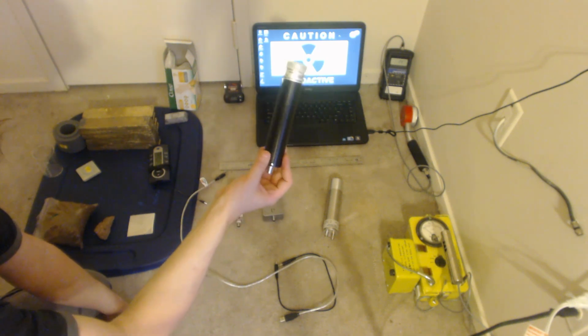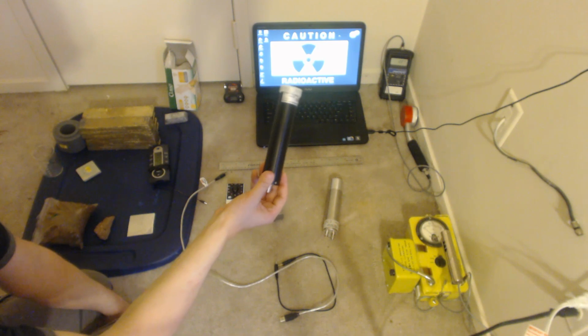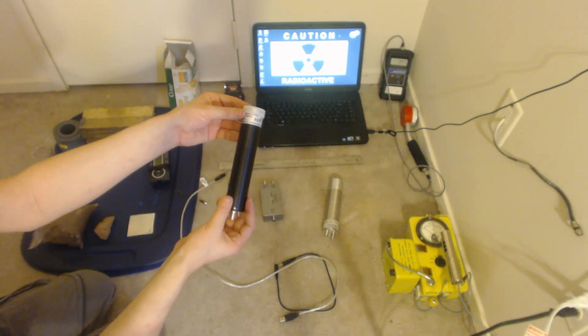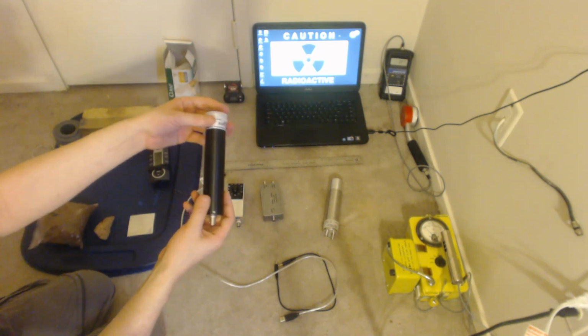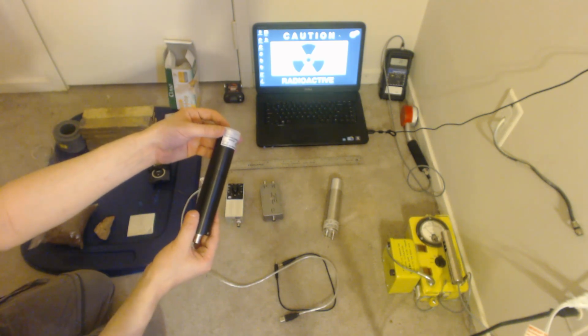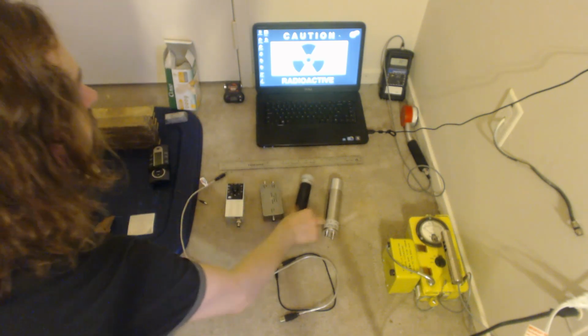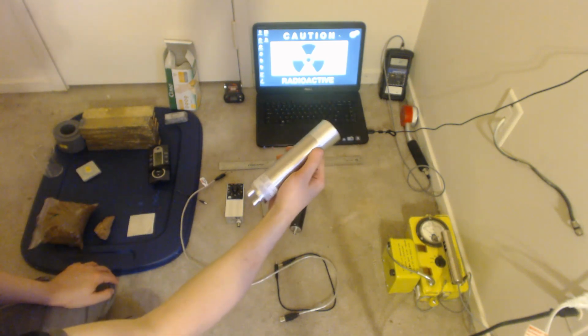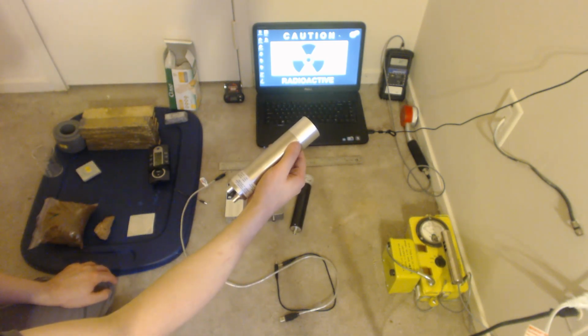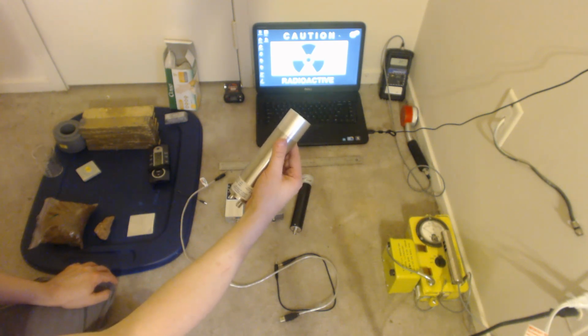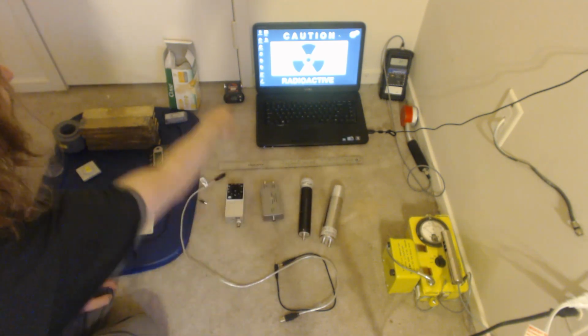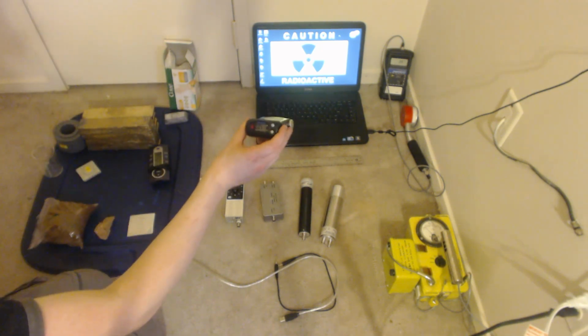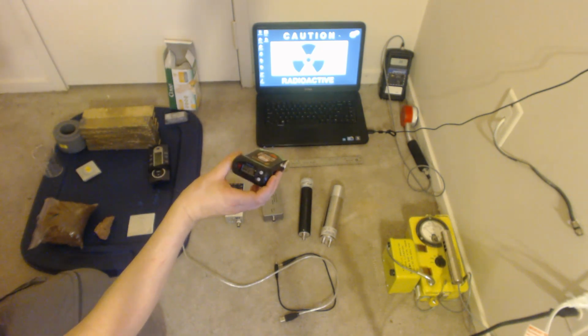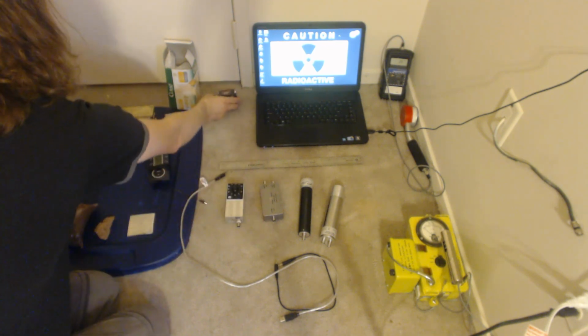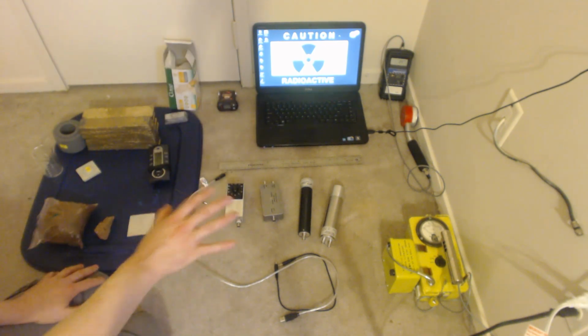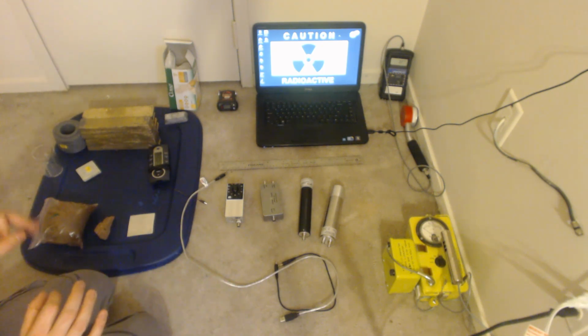Its ability to detect, meaning if 100 gamma rays at 500 kilo electron volts hit it, it might only pick up like 5 of them, 3 of them maybe. Whereas if 100 of them hit it at 10 kilo electron volts, it would probably pick up like 80 or 90 of them. This guy right here has a range of about 12 kilo electron volts to approximately 3,500, maybe even a little bit more. Not bad. Same with that guy right there. My Polimaster is 40 kilo electron volts to 3.5 million electron volts. Not bad. But anyway, that's your basics on your crystals, your kind of crystal 101.